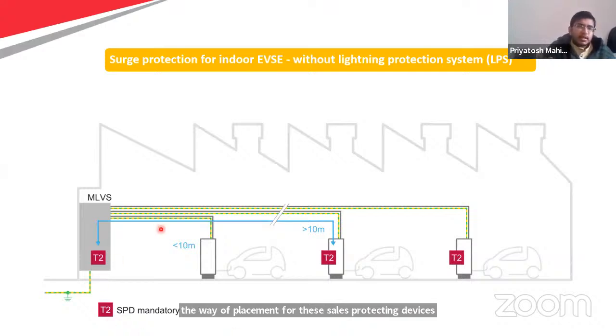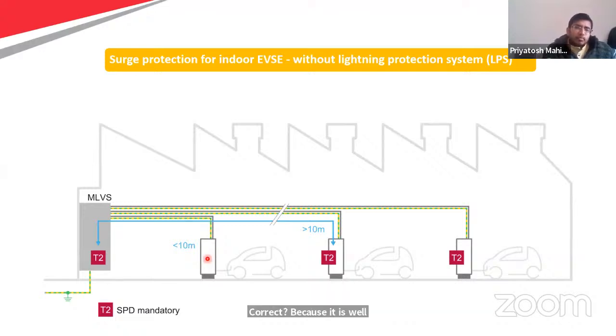You see here that T2 is the SPD, and this is mandatory. If you place it here, as you can see, this charging station's distance from it is less than 10 meters, so you don't require a separate SPD for this charging station. Protective engineers understand that when a surge happens, if it affects your charging station, it will be saved by the SPD if the distance is less than 10 meters. So it will be protected by this, because it is less than 10 meters.